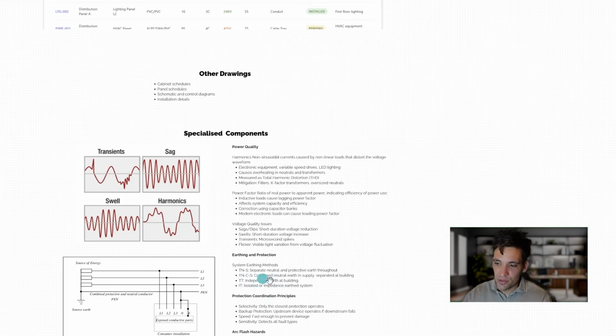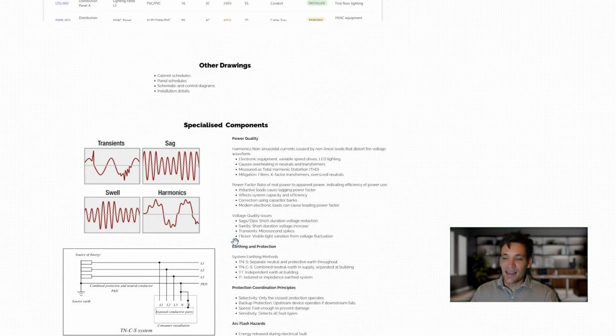They're referred to as TN-S, TN-C-S, and so on. TN-S is where throughout the entire installation you have a separate neutral and a separate earth. A TN-C-S is where you have a link between the neutral and the earth at the load. So instead of running a separate earth cable, you're eliminating the earth cable and you have a link between the neutral and the earth at the load. And in some systems, you also have an independent earth at the building, separate from the supply earth.